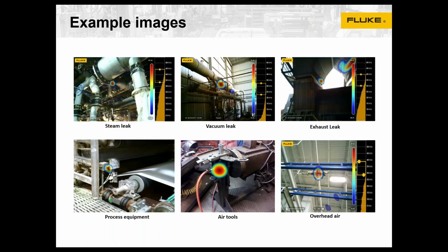Here are some example images that we'll run through of a variety of different types of leaks, different environments. Keep in mind that all of these are from running plants, in some cases very, very noisy. So the product is very effective at mapping leaks, even in the presence of high ambient noise. One example of that is over here in the exhaust leak. This would represent sound level or ambient noise down in the audible range. The tester can effectively ignore all that and only map what is in this range here. And it is a touchscreen operated tool, so it's very intuitive to move this around up and down to best pinpoint leaks in a wide variety of applications.